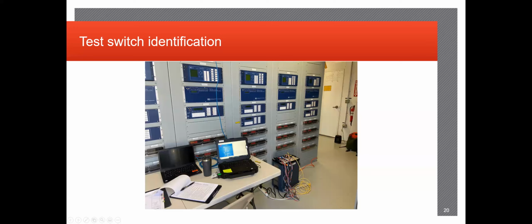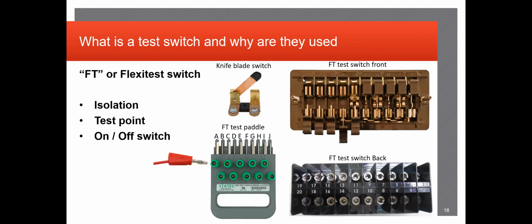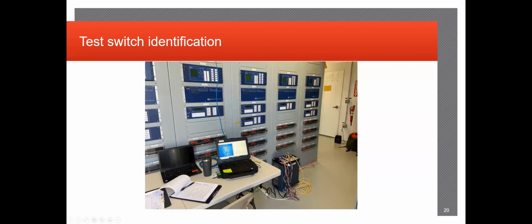Has a test set up, is ready to go, plugged in. So yeah, I guess all he's missing is plugging into the test switches. So going back to what I was talking about with the accessibility for the test paddles. Once the relay is properly isolated, all these switches should be open. So the test paddle can easily plug in right into the front, and you can easily plug in all your test leads for your current and voltage sources from your test set directly into the paddle, which will go up into the relay and allow you to properly test it.